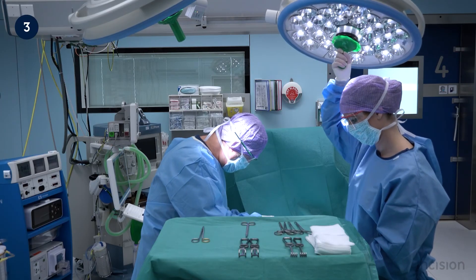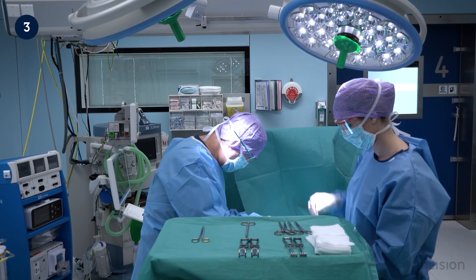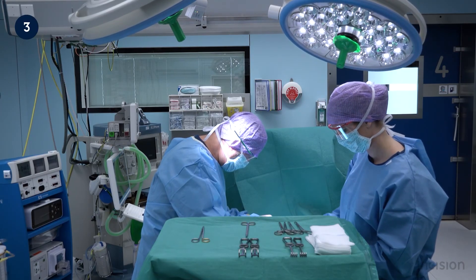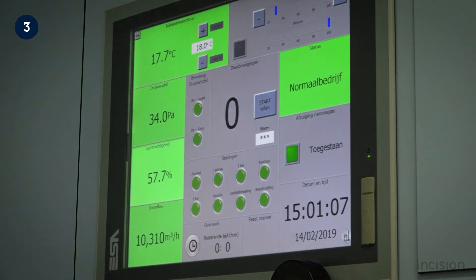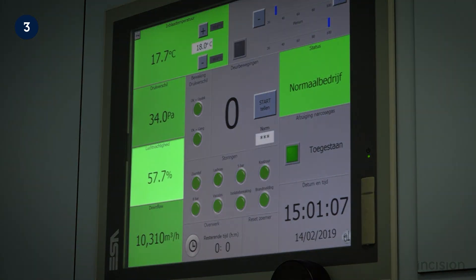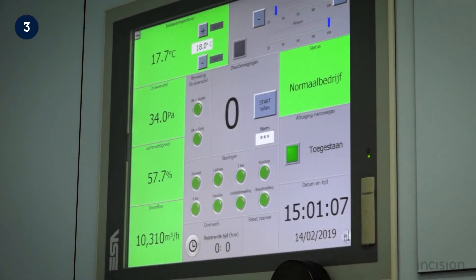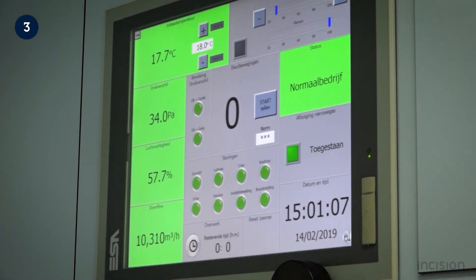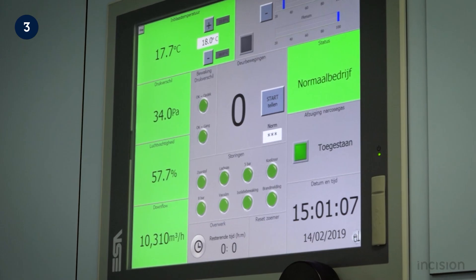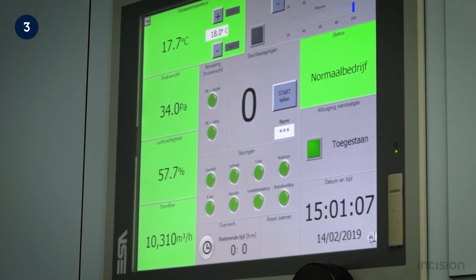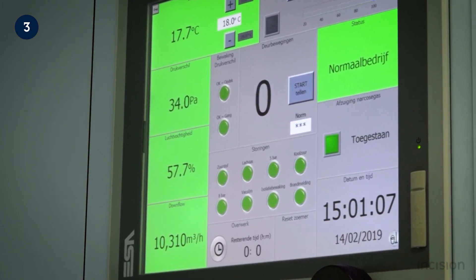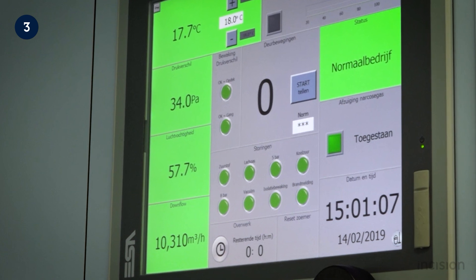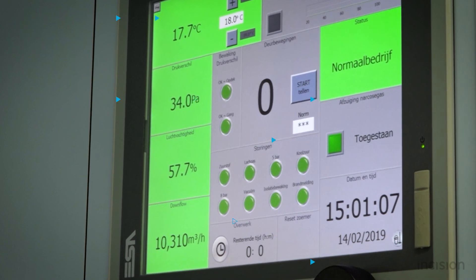Research shows that a cool environment improves concentration and prevents irritation within the team. Additionally, bacteria, viruses, and other organisms grow and reproduce more slowly at lower temperatures. Humidity should be maintained between 30 and 60 percent; higher humidity may cause condensation which can jeopardize sterility, while lower humidity on the other hand may generate static electricity, which may lead to electrical shocks or fire.